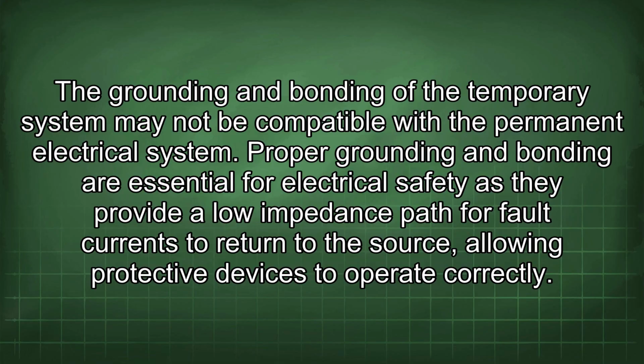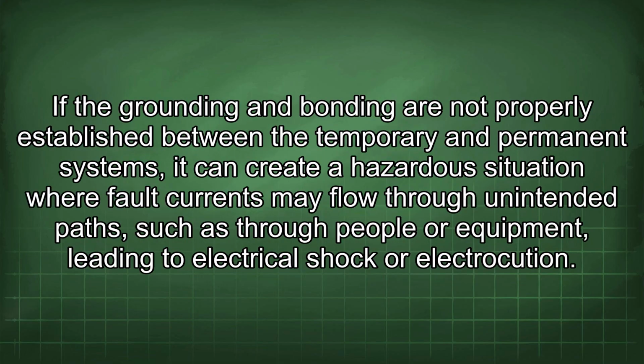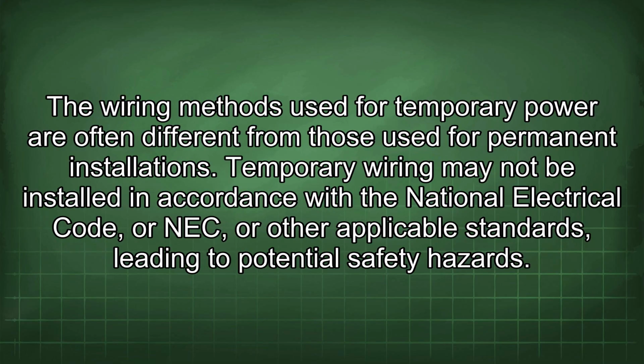The grounding and bonding of the temporary system may not be compatible with the permanent electrical system. Proper grounding and bonding are essential for electrical safety as they provide a low impedance path for fault currents to return to the source, allowing protective devices to operate correctly. If the grounding and bonding are not properly established between the temporary and permanent systems, it can create a hazardous situation where fault currents may flow through unintended paths, such as through people or equipment, leading to electrical shock or electrocution. The wiring methods used for temporary power are often different from those used for permanent installations.